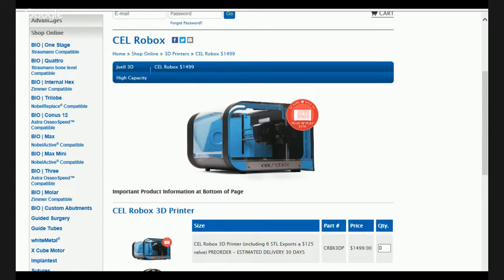One of the things that this printer has that most 3D printers don't is a cartridge, a reel of filament. It's a filament-based printer, but the reel has a chip in it that keeps track of how much filament is being used. It has things such as a flow rate measurement that informs you if the filament is flowing properly. It has a very high resolution. It can print down to, according to the manufacturer, 20 microns. I would say realistically 50 microns, but that's certainly enough to print surgical guides.